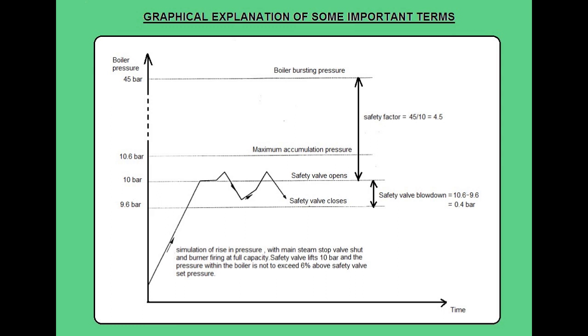Accumulation pressure: the maximum pressure allowed to be accumulated in the boiler when the safety valve is fully lifted, with the main steam stop valve shut and the boiler firing on full load.